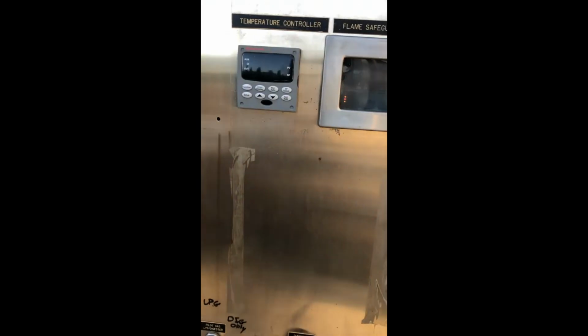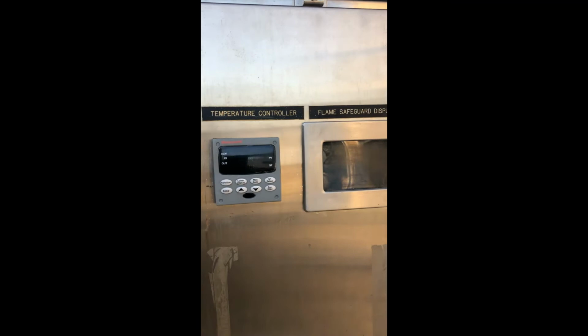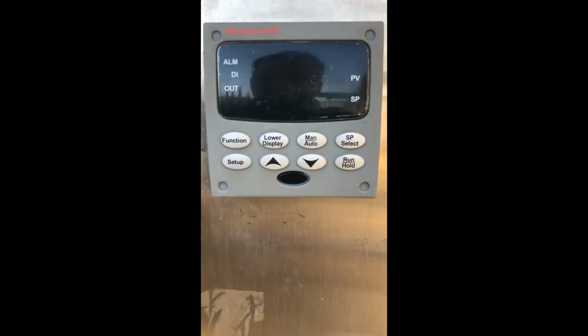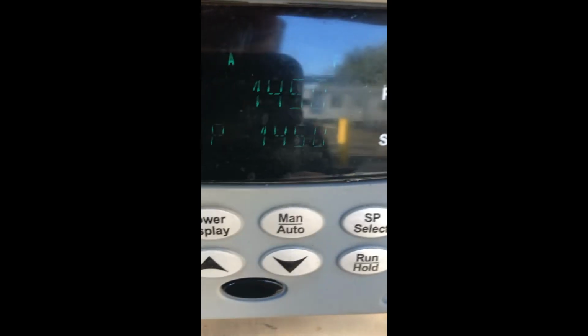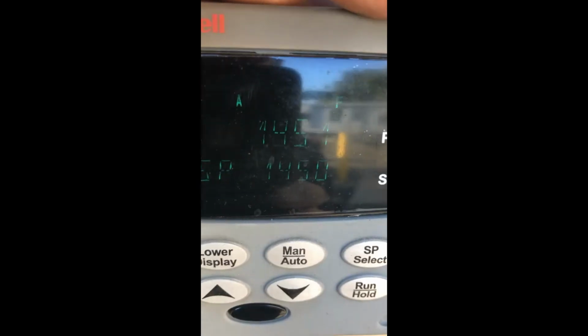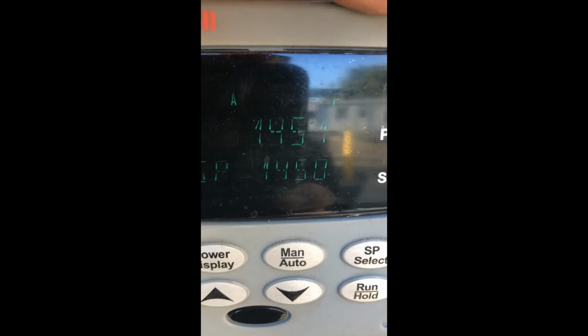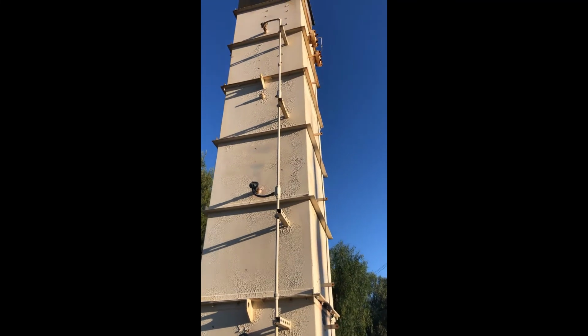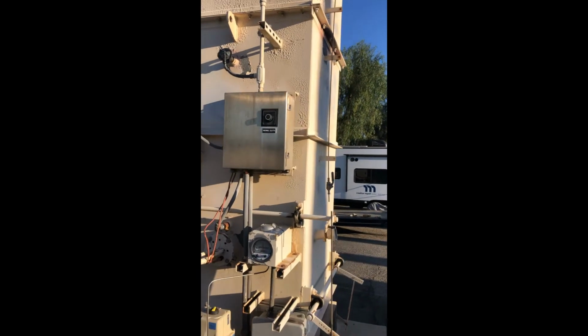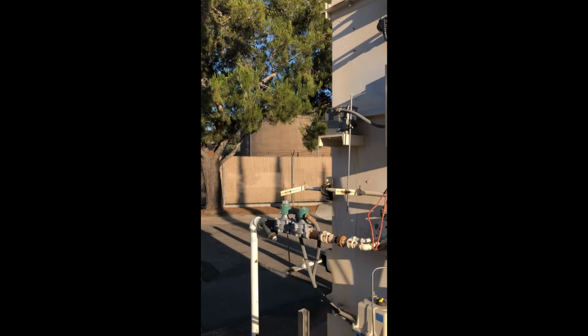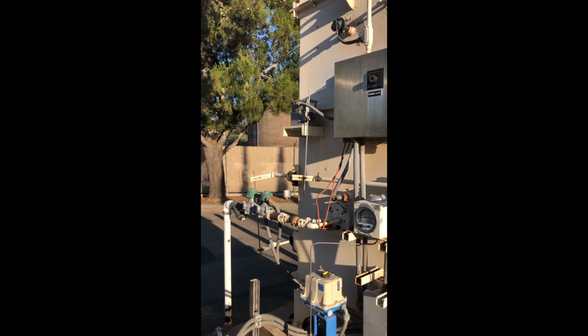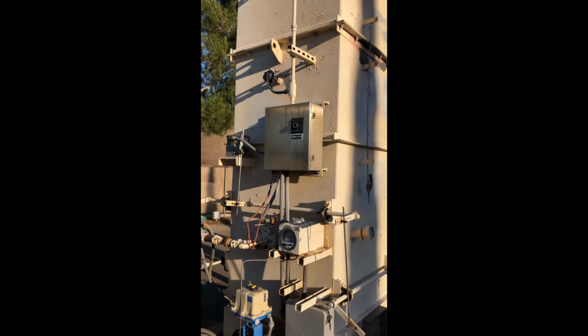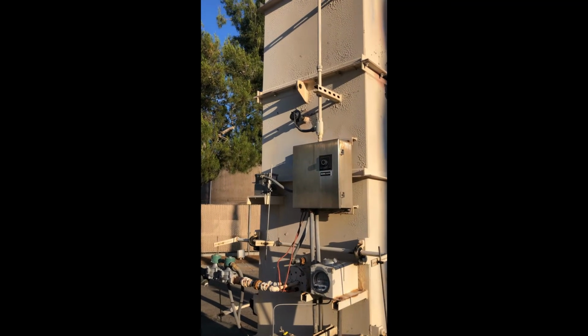Now, we talked about this a little bit in the class. This is a standalone closed loop PID controller. This one doesn't have a PLC. And you can see that there's a set point of 1950. This thing's doing a pretty good job. It's maintaining it right there on the set point. The process variable is these thermocouples that are going up the stack here. There are 3 of them, and the operator can select which one it's actually going to use. The reason there are 3 is because if we're burning off a lot of gas, then we have to use the thermocouples that are a little bit higher on the stack, because the flame goes up higher. But the process variable is the temperature of the flare measured by the thermocouple.